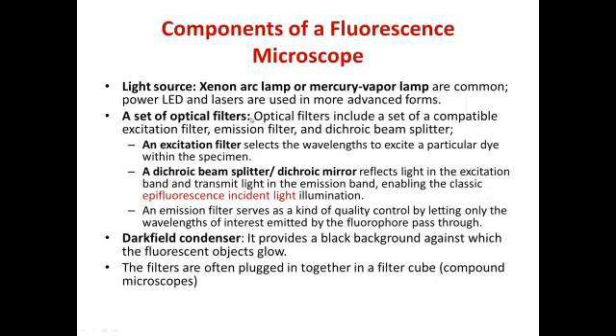After the light source, a set of optical filters are used. These include the excitation filter, the emission filter, and the dichroic beam splitter or dichroic mirror. The excitation filter selects the wavelengths to excite a particular dye present within the specimen. We can choose this filter by our own will because we know which color we have given to the sample.